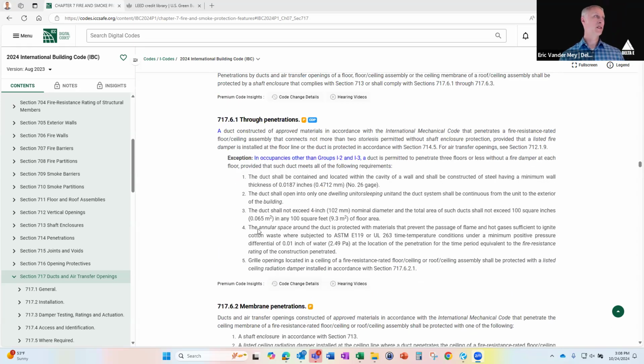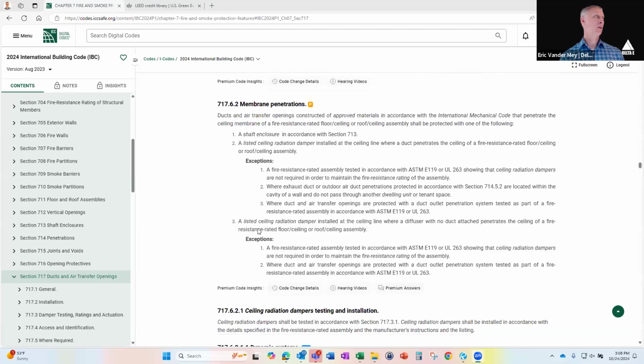So the new provisions that were added into the 2021 code is really this section in 717.6.2, membrane penetrations. These penetrations are typically in the bottom surface, the ceiling surface of a rated floor ceiling assembly. And so they have this whole section about you can penetrate if you have a shaft enclosure.